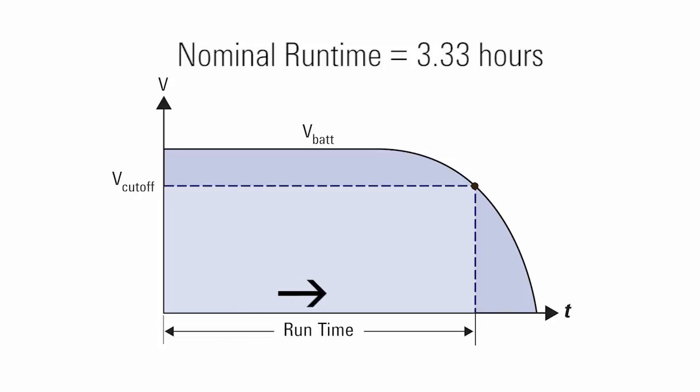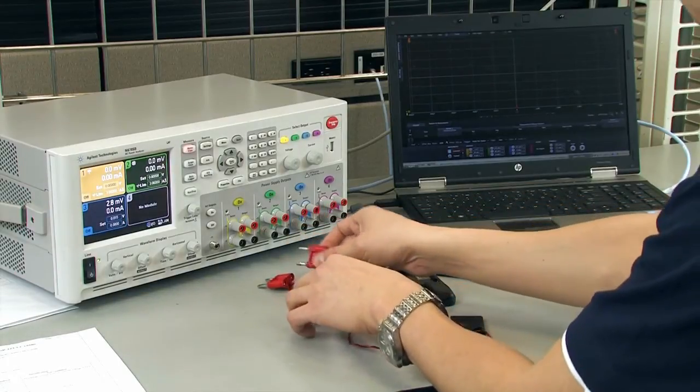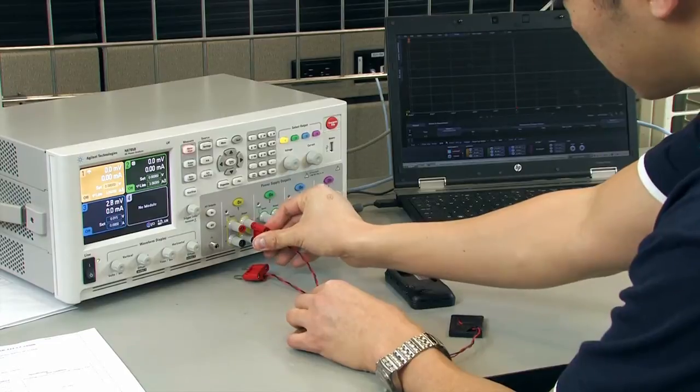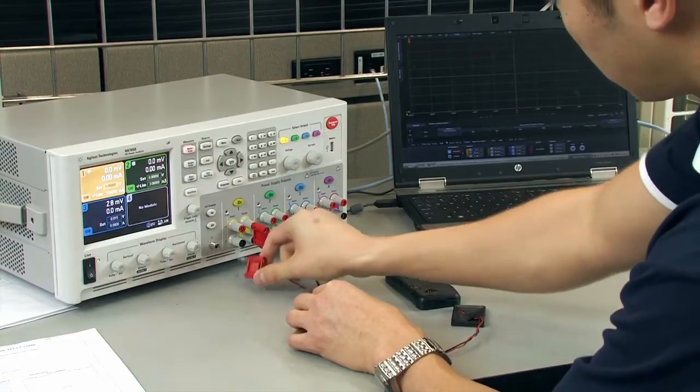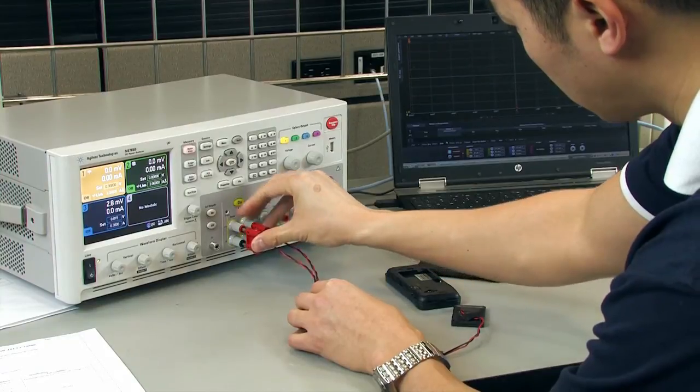It is also worth noting that the measured energy rating can differ from that based on the stated nominal voltage, as the actual battery run-down voltage profile may lead to a slightly different result. Precisely controlling test conditions while accurately logging both the battery's current and voltage assures accurate and consistent results when determining the battery's capacity and energy ratings.